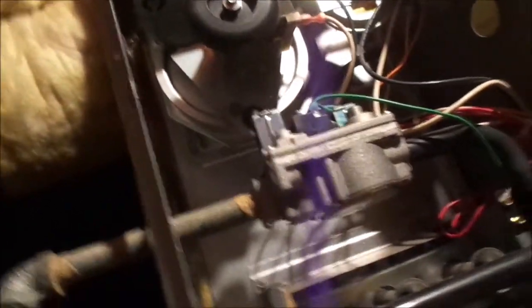Got something I gotta check here. And the inducer — vacuum. Then this thermostat up here, it's a resettable thermostat. That came on but it didn't even heat. Should have that igniter ignite — I didn't check the continuity on it, but that igniter looks like it's good.